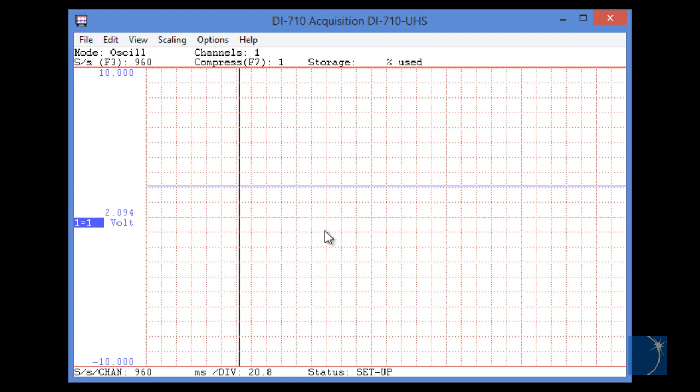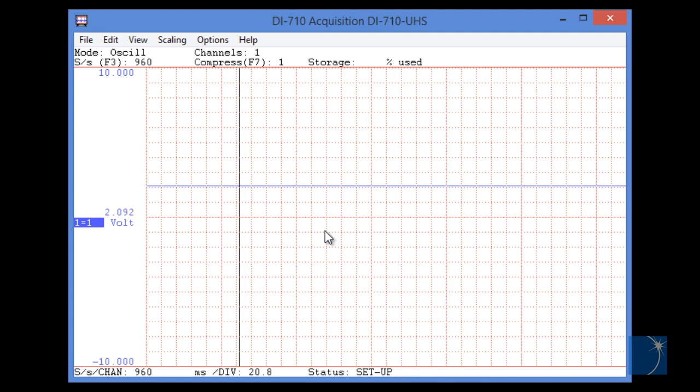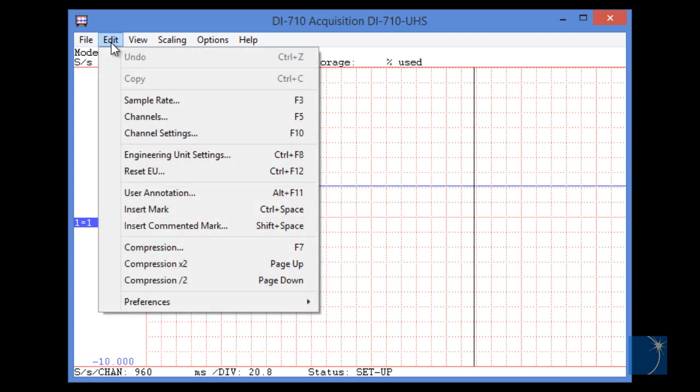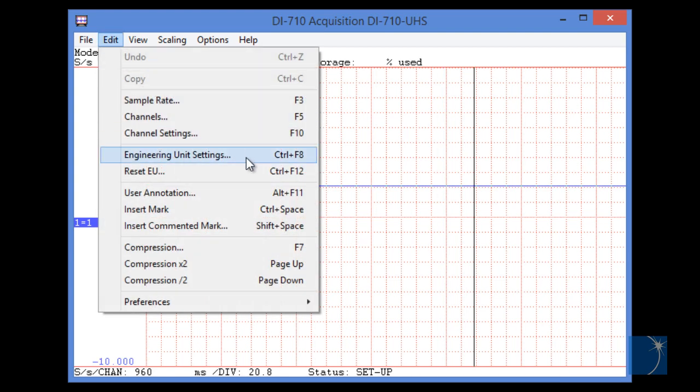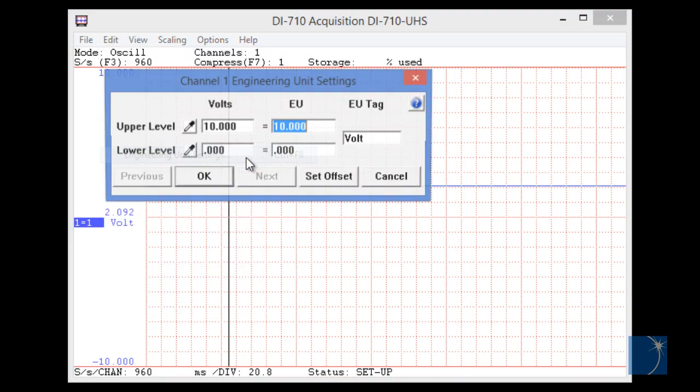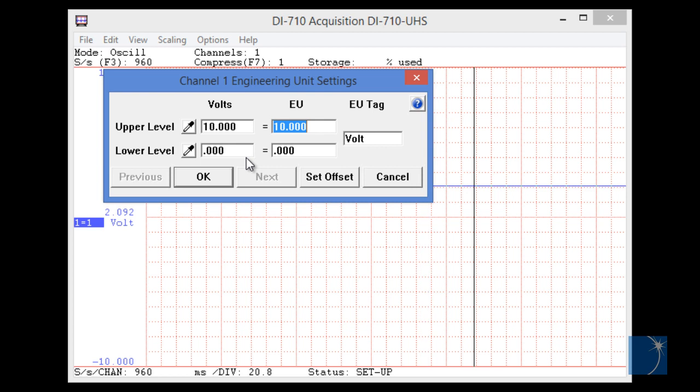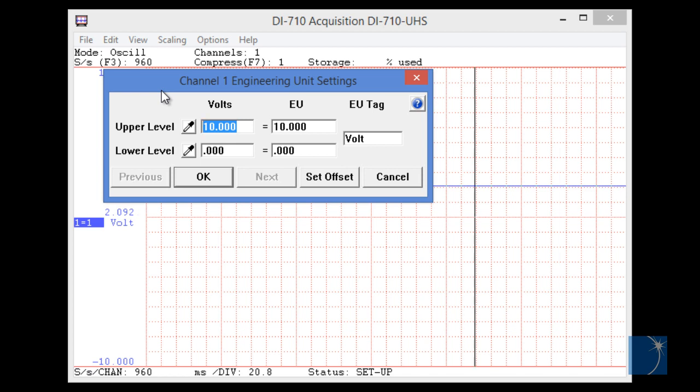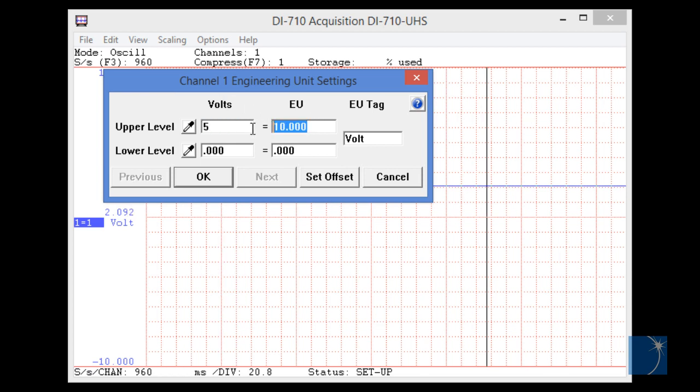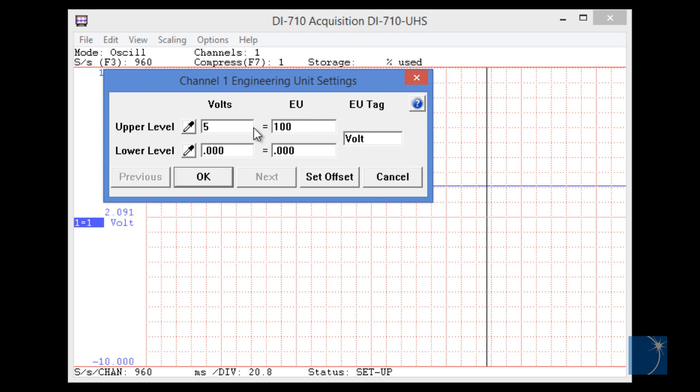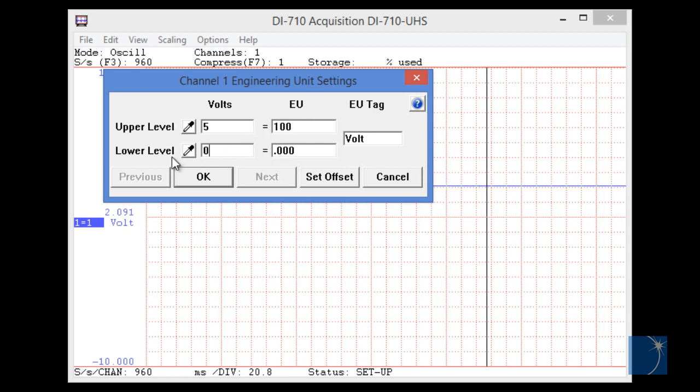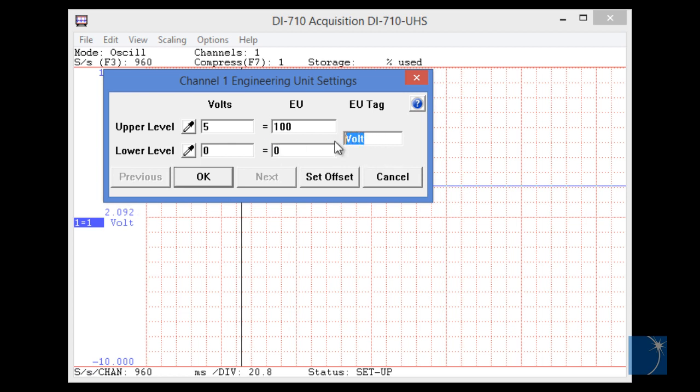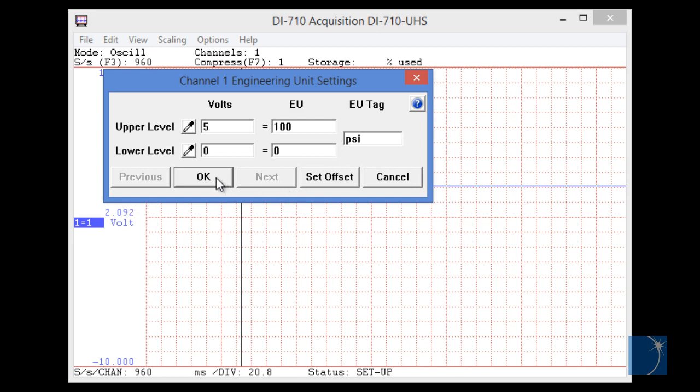With the single channel displayed, we'll scale to display engineering units, in this case, psi. To do so, we'll choose Engineering Unit Settings from the Edit pull-down menu, and since we know that our transducer outputs 5 volts at 100 psi, we'll set 5 equal to 100, and 0 equal to 0, since we have 0 volts out at 0 psi. We'll change the EU tag to psi, and click OK.